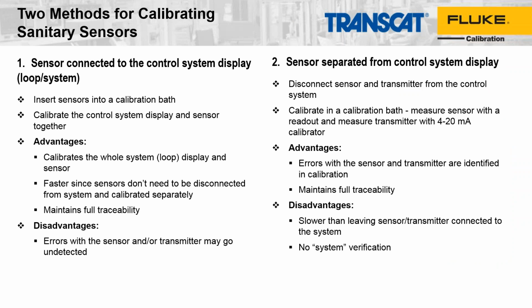What we want to talk about is a couple of different calibration methods that are possible using this type of calibration system. The first method is where the sensor is removed from the pipe system in the factory or the facility, and the sensor, along with the transmitter, the assembly, is kept together. The sensor is put into a bath, and then the transmitter and temperature sensor are calibrated as a system by comparing the bath temperature display with the control room display or the controller, if there's a local controller connected to the temperature sensor. We'll go through that in a little more detail. And I need to talk about the advantages and disadvantages.